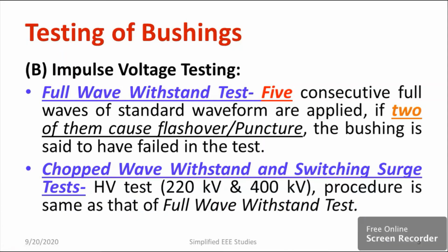Let's discuss the second procedure, that is the chopped wave withstand and switching surge test. Here, you have to adjust the wavefront and wavetail resistance of the impulse generator in such a way that you produce chopped waveforms. The procedure is similar.